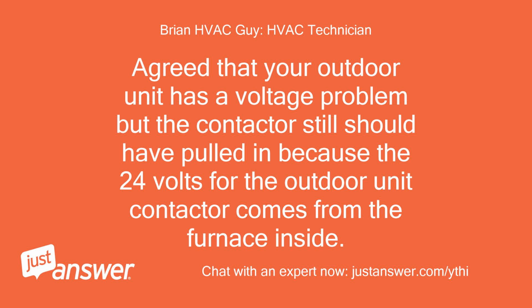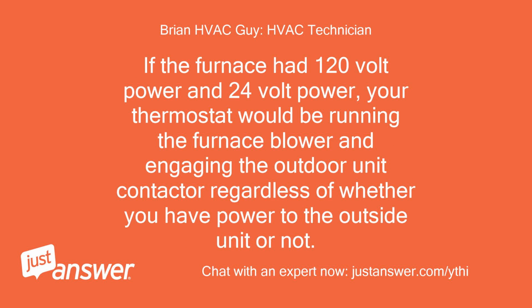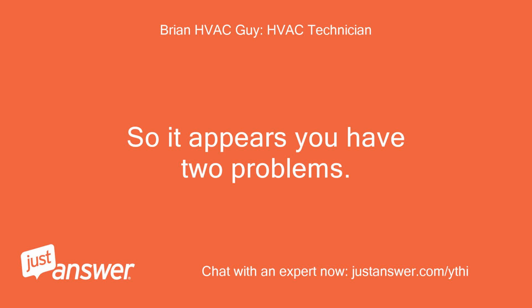Agreed that your outdoor unit has a voltage problem, but the contactor still should have pulled in because the 24 volts for the outdoor unit contactor comes from the furnace inside. If the furnace had 120 volt power and 24 volt power, your thermostat would be running the furnace blower and engaging the outdoor unit contactor regardless of whether you have power to the outside unit or not. So it appears you have two problems.